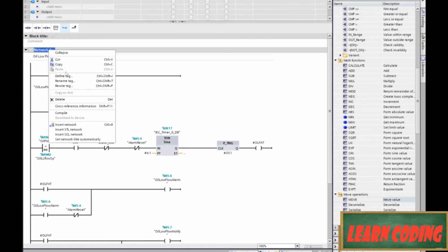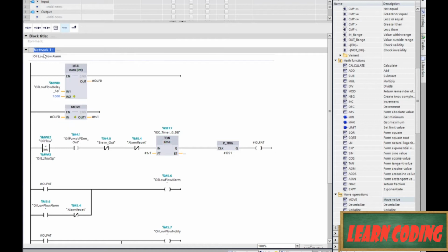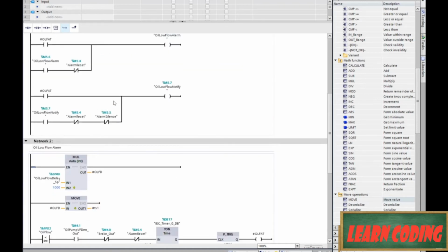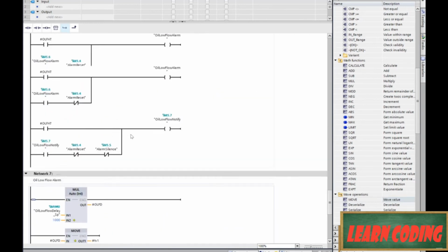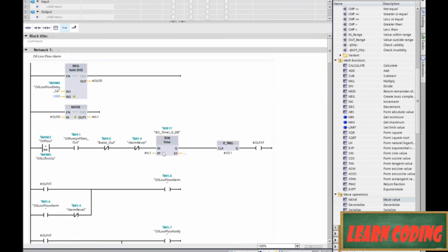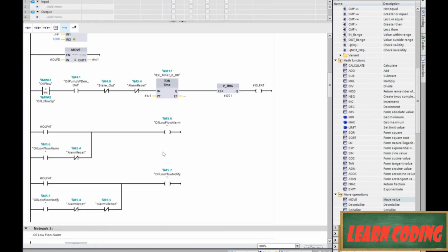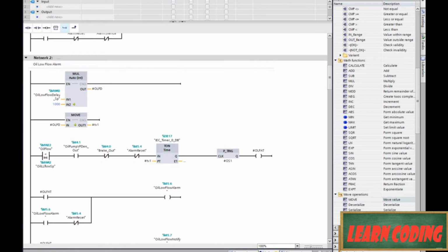And now let's go ahead and copy, and I'm going to paste 1, 2, 3, 4, 5. Give ourselves 6 more of those because we've got a few more alarms to get through. But now that we've got the first one done, the rest will be easy. Next thing we want is we're going to do an overcurrent alarm. And we're looking for the current to be anything over 550 amps. So pretty simple. Let's come over here and rename this.